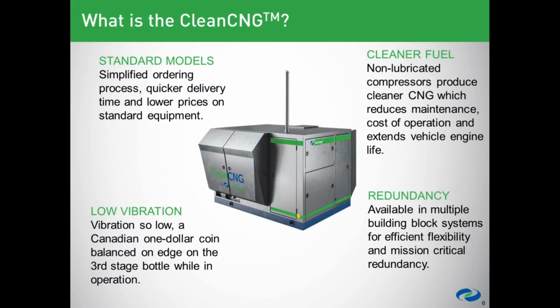Another key area was vibration, because that's foundational to a unit's maintenance and reliability. And so everything from piping layout to various other techniques were used to reduce the vibration to a point where I myself stood beside one on a gravel pad. It was unanchored, 250 horse, running full out, and balanced a Canadian $1 coin on the main part of the unit, about halfway up. So center of gravity, you know, this wasn't way down, this was up high on the unit as it ran full out. And if any of you are familiar with the Canadian $1 coin, it is much thinner than even, say, a euro.